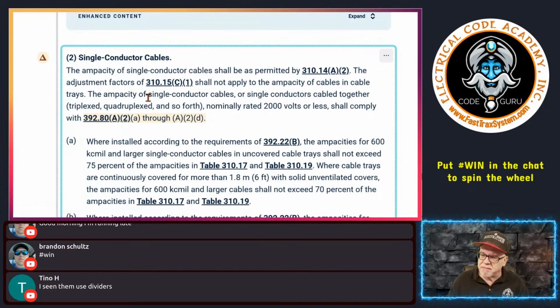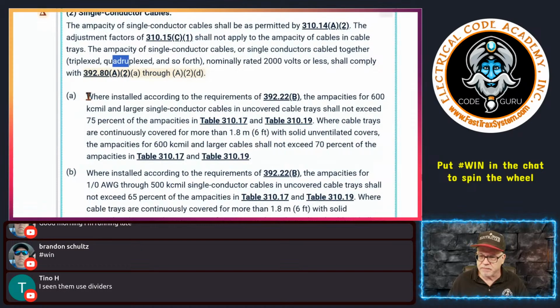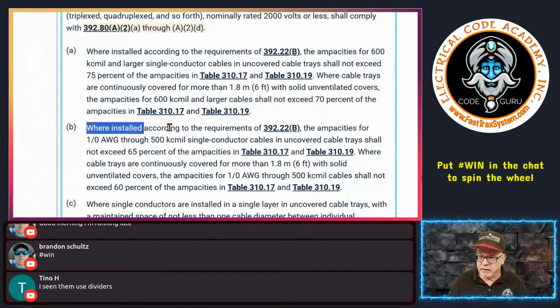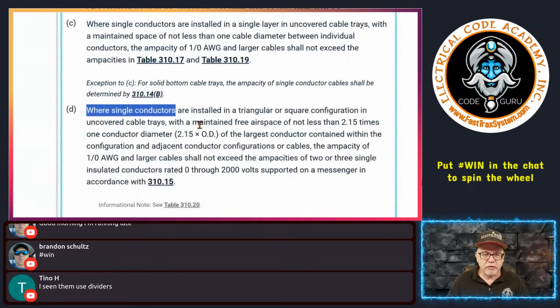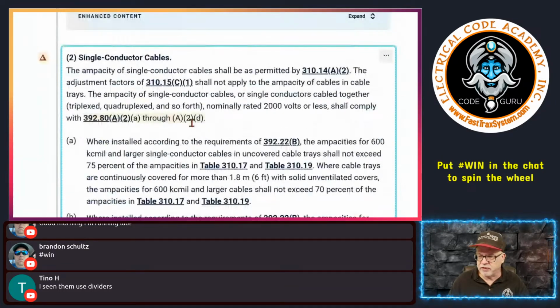Okay, so it says the ampacity that applies in this scenario, the ampacity of single conductor cables and single conductor cables together in triplex, quad, and so forth, nominally rated 2,000 volts or less, shall comply with 392.80(A)(2)(a) through (A)(2)(d). So they have to apply here. Okay, so here, here, here, and here. All right, so we're going to go through each one of these, pretty straightforward.